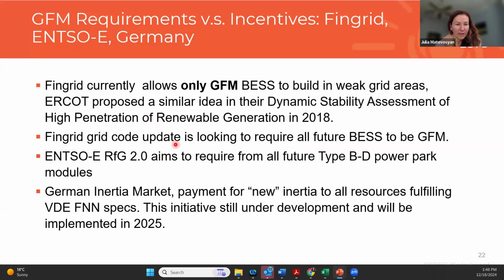FinGrid, again, is looking to update the grid code to require all future batteries to be grid forming. ENTSO-E will require all future type B to type D power park modules to be grid forming.